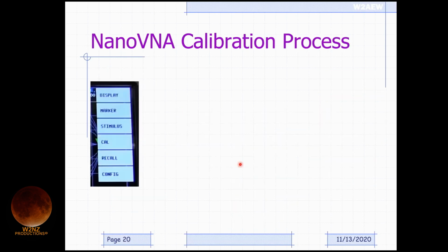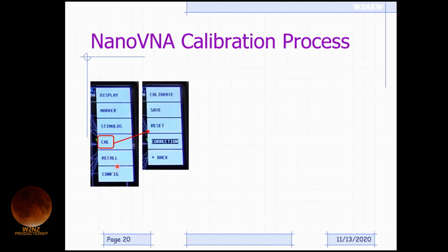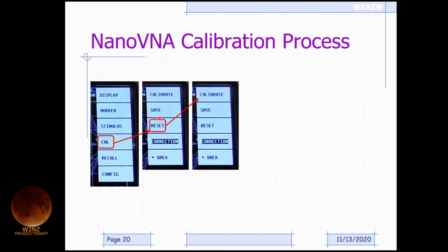So here's how you actually do the calibration. That's also a good walkthrough of the menu process. Just tapping on the display or pushing down on the rocker, you'll come up with the menu. From there, if we hit Cal or Calibrate, depending on the version of the menu, it'll say one or the other. That brings up the calibrate menu. From there, you can hit Reset to reset the existing calibration, and then go and hit Calibrate.